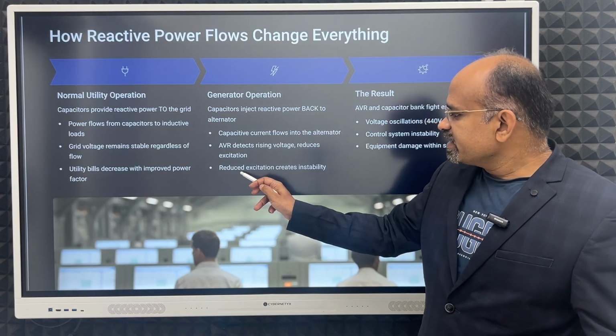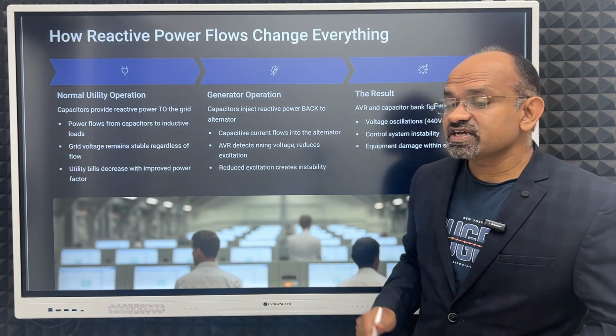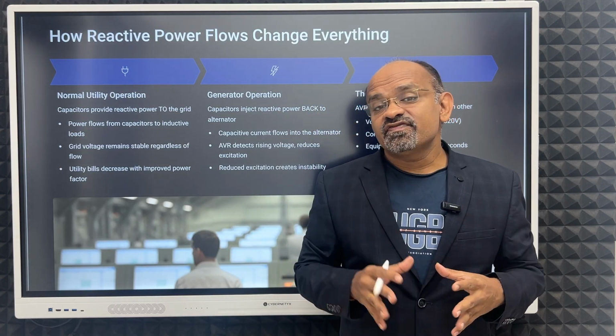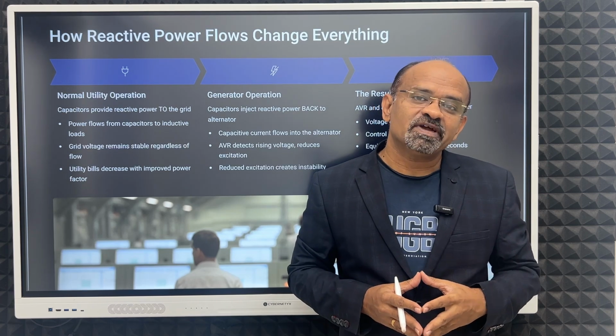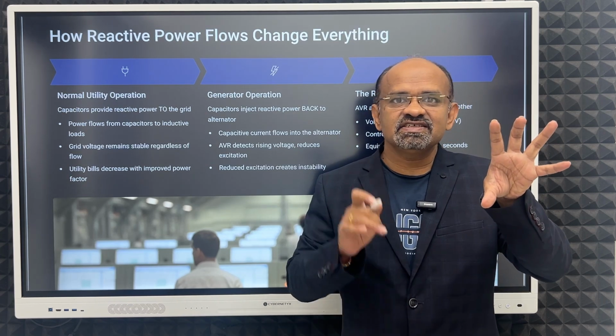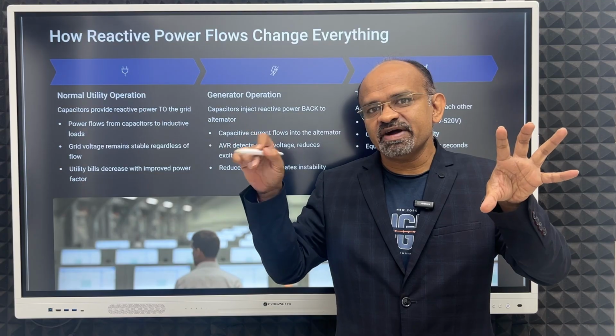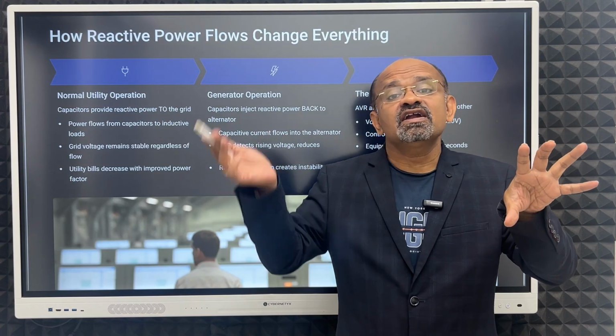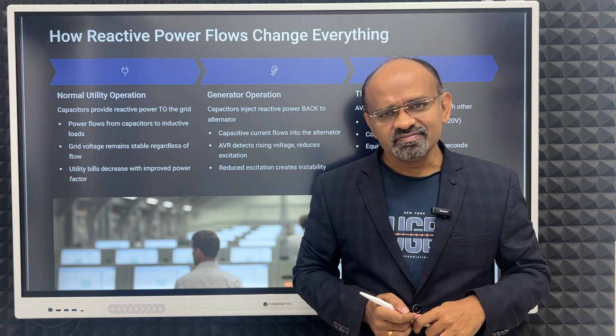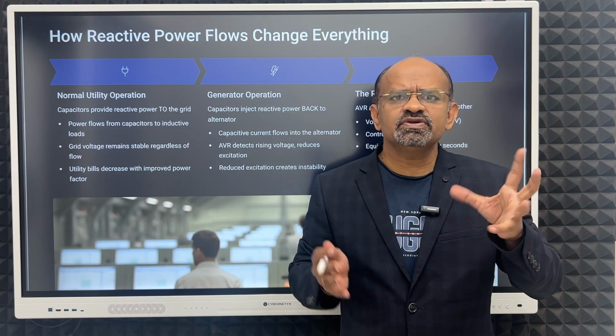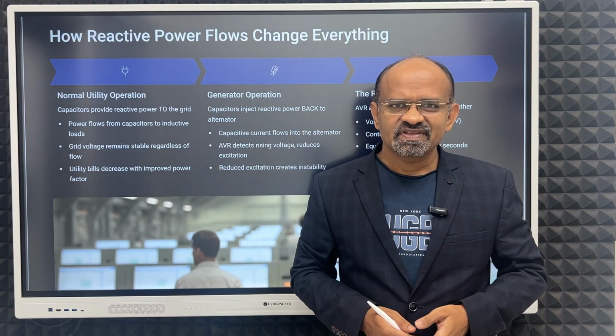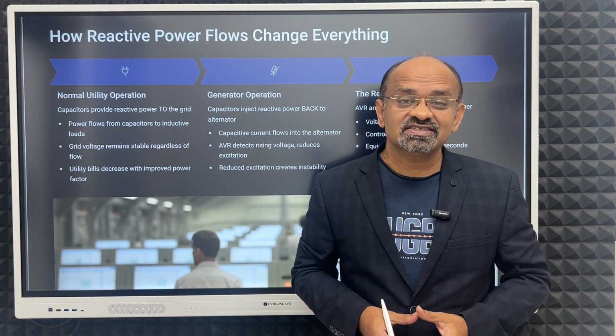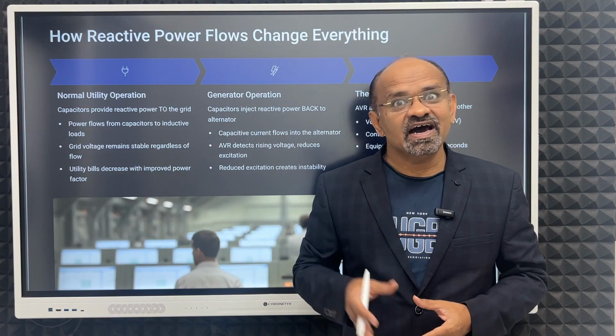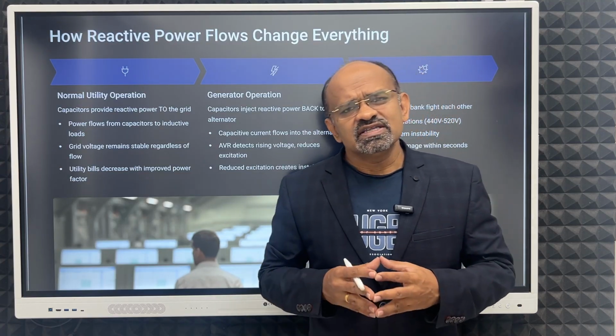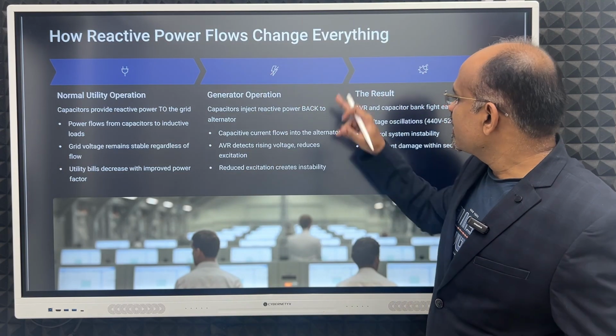Then reduced excitation creates instability. If voltage is not proper, since power is constant—P equals voltage multiplied by current, V into I—then current will go up. Your equipment will not work properly; it will heat up, causing heat losses, I-square-R losses, because I is going up while R is constant. So these are the problems caused by the capacitor.